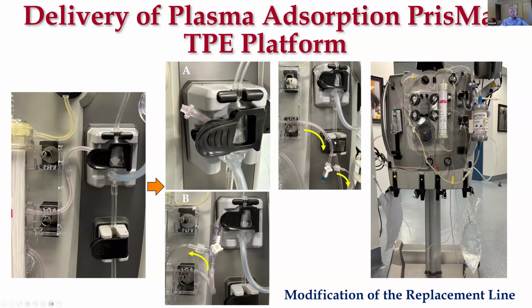Now remember that all the replacement solution to the dog is going to occur up here in this stopcock that you put in, so now we've sealed that line. Everything is aseptic, and so now we have the sealed line. Then we put a stopcock on the replacement line, and then we put a line on the other end of the stopcock that directs that replacement fluid directly into the collection bag. So for every drop of fluid that comes out of the patient's plasma is replaced by a drop of fluid that comes from the replacement bag directly. And then you don't have to put plasma, you can just put water in this bag, and the machine won't care.